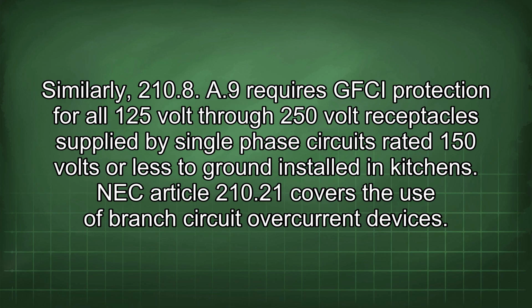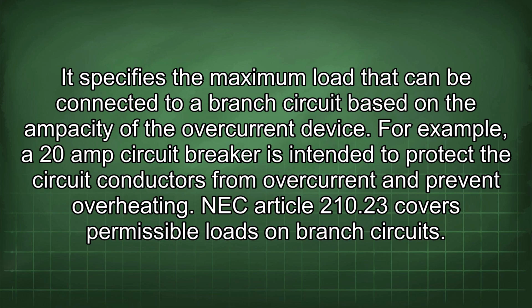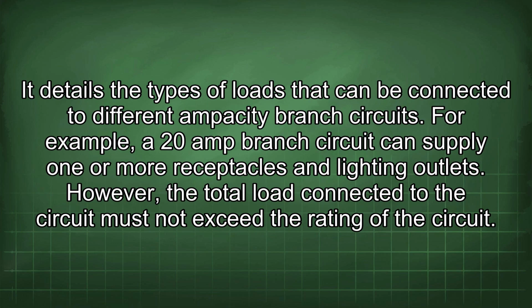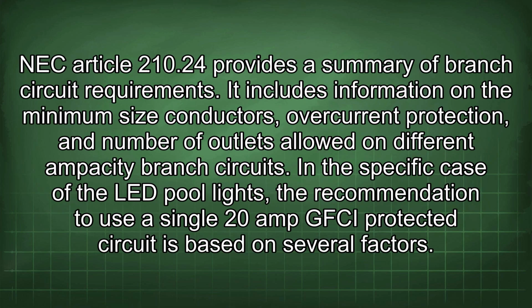NEC Article 210.21 covers the use of branch circuit overcurrent devices. It specifies the maximum load that can be connected to a branch circuit based on the ampacity of the overcurrent device. For example, a 20 amp circuit breaker is intended to protect the circuit conductors from overcurrent and prevent overheating. NEC Article 210.23 covers permissible loads on branch circuits. It details the types of loads that can be connected to different ampacity branch circuits. For example, a 20 amp branch circuit can supply one or more receptacles and lighting outlets. However, the total load connected to the circuit must not exceed the rating of the circuit. NEC Article 210.24 provides a summary of branch circuit requirements. It includes information on the minimum size conductors, overcurrent protection, and number of outlets allowed on different ampacity branch circuits.